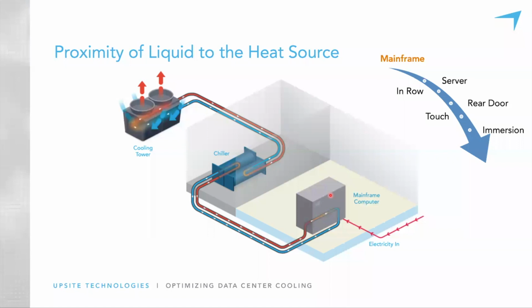So starting here in the mainframe days, we've got a big box sitting in the computer room on the slab or the raised floor, and we've got chilled water. We've got water flowing through the chassis, picking up that heat, taking the heat out of the chassis with liquid, and likely taking it to a chiller, and then with a heat transfer, the process that occurs in the chiller, that heat is transferred to another liquid, to the condenser water, and that condenser water carries the heat out to a cooling tower of some form where the environment can pass through and the heat is ultimately rejected to the atmosphere. So in this case, we had these two loops of liquid and then the final loop of air to remove the heat from the room. And so liquid was very close. It was up against the source of the heat in the computer room.